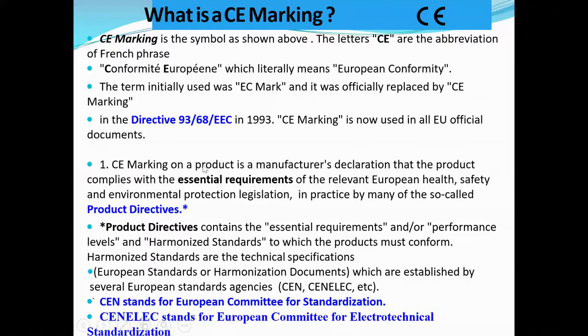CE marking on a product is a manufacturer's declaration that the product complies with the essential requirements of the relevant European health, safety and environmental protection legislation, in practice by many of the so-called product directives. I have told this during your European regulatory system lectures as well. Europe always follows directives, and the US always follows the 21 CFR parts. So you have to remember the difference between the US and Europe: there it is CFR parts, here it is directives.